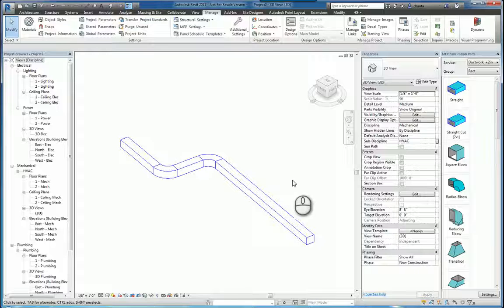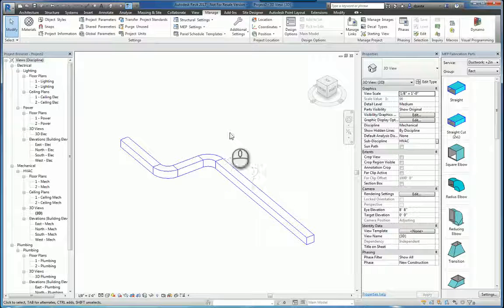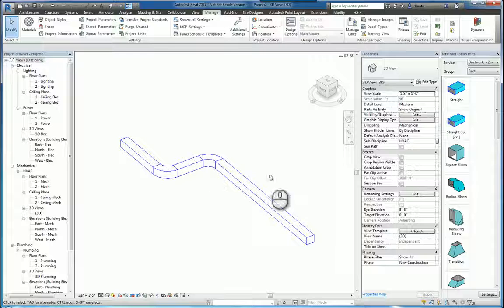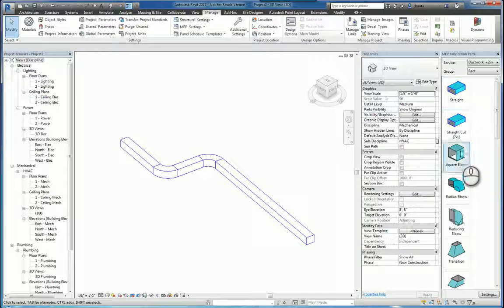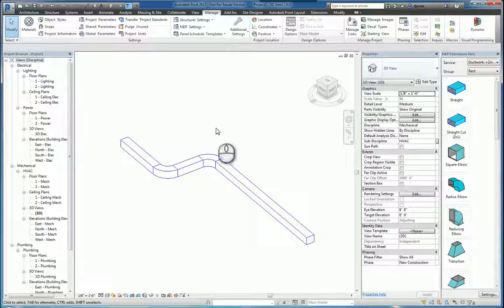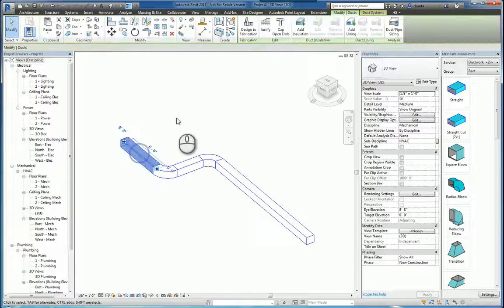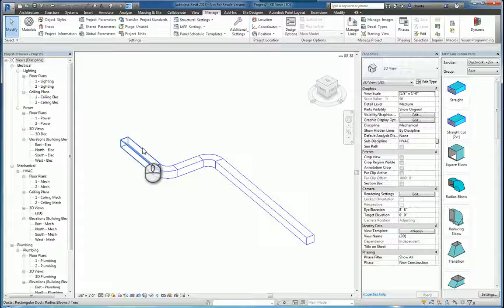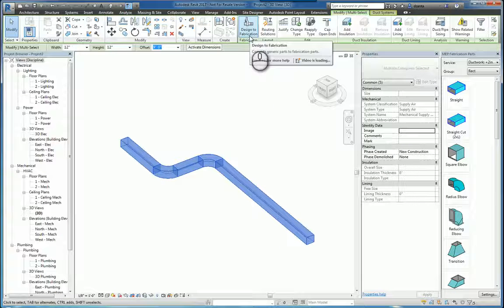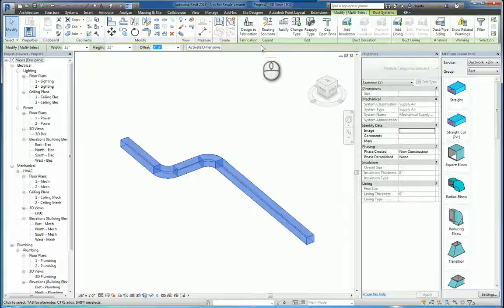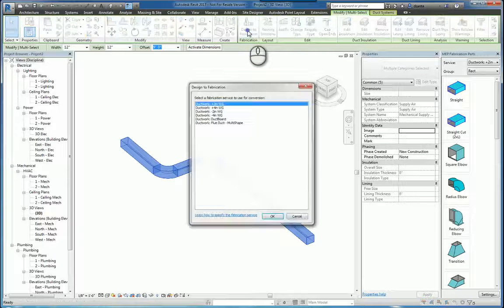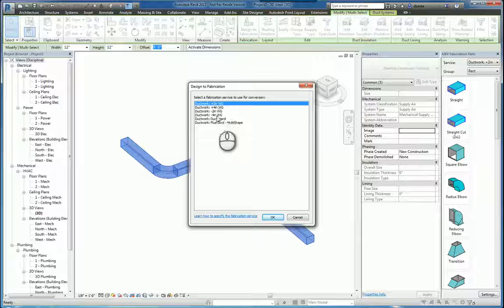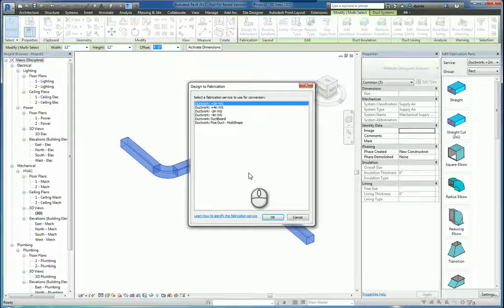If you design your Revit model MEP systems with the standard content, you can actually switch this content to fabrication content without actually having to manually draw them using the library that's given to you. So for example, I can select either a duct or I can hit tab and select the entire system, and I'll get a contextual tab called modify multi-select. In here you'll see fabrication panel and you can click design to fabrication. It'll ask you which particular service you want to work with, you select what you need and click OK.